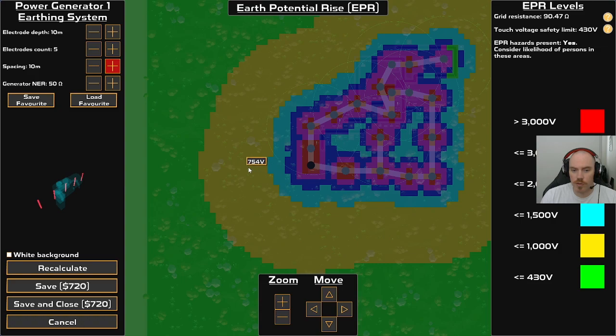So you want lower voltage levels, about 400 or less. The way to do this is to reduce your grid resistance, the total resistance, by adding more copper in the ground. Like you put copper in the air to reduce resistance in aerial lines, you just want to put more in the ground.